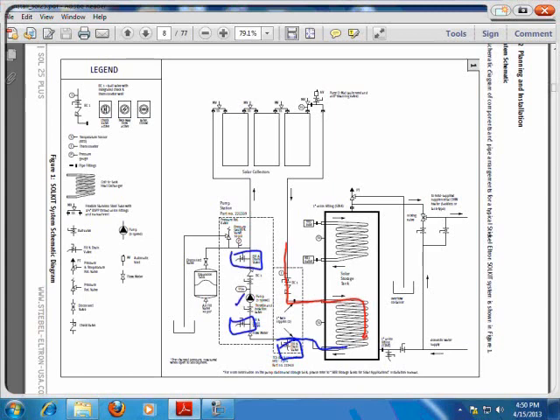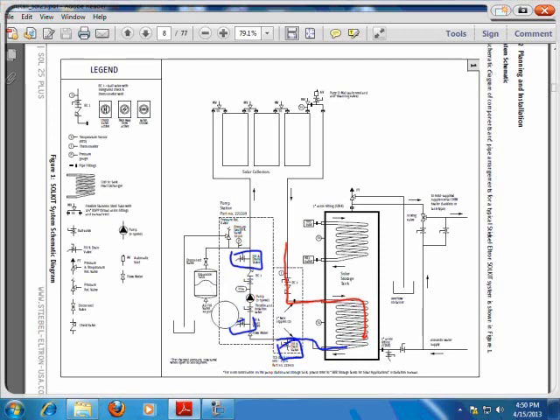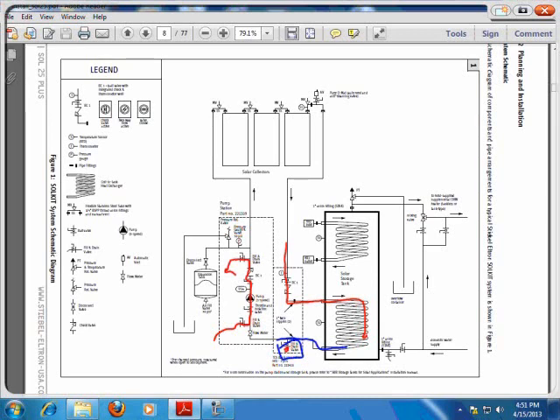And the reason we put fill valves here and there is so that I can isolate a problem. If and when that pump fails, I can shut these two valves off. This valve here and that valve there. Remove the pump, put a new pump in. And then what I can do is open these two valves. So I open valve on BC1 and then this downward valve body right there. Then what I can do is I can add fluid with this valve closed. So this valve is still closed. I can fill water in, fill this void, have it come through, and then drain. Now I have a filled system, so I don't have to adjust the rest of my solar thermal system if I have a pump that needs to be replaced.